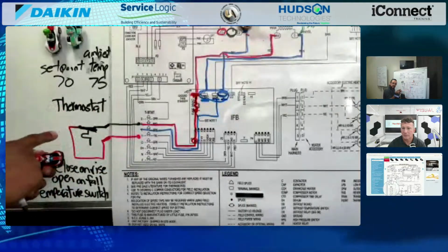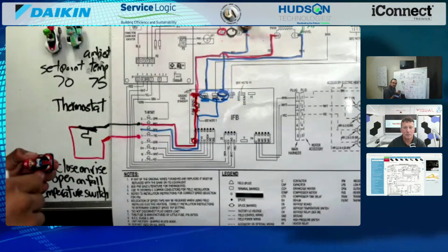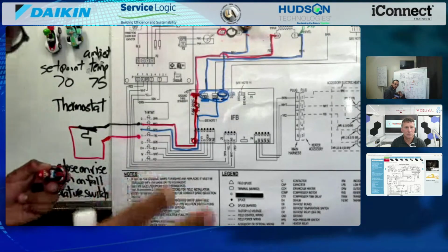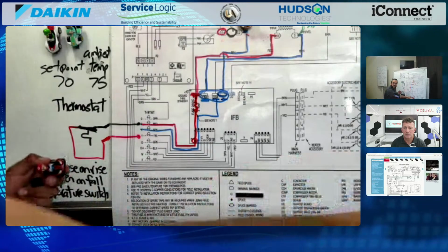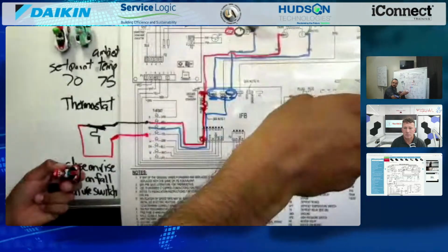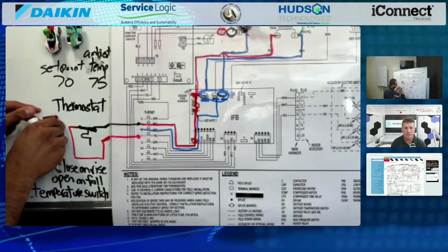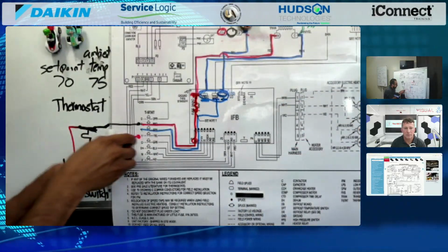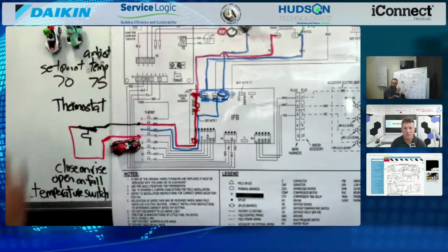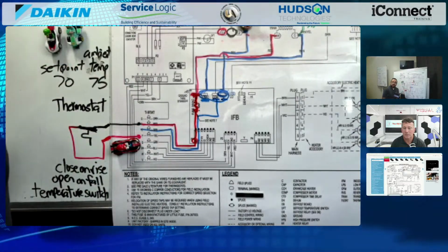Internally, when I have a call for cooling, R is like, hey Y wire, here you go, I'm going to close the path. Mario's going to go through you because you're the call for cooling. So then Mario goes, and now he ends up on the yellow wire, right? So now yellow wire has 24 volts.